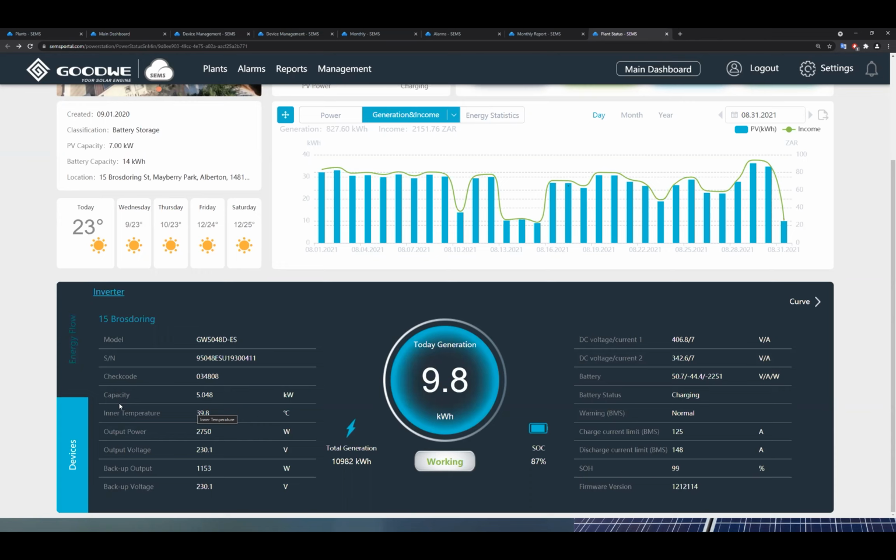Sometimes when we don't see anything here or any problems here, we do export that data, because then we can see 1 minute interval data, and that will give us a better indication of exactly what has occurred. As you'll see, this is live snapshot data. So it's the current live snapshot of what was going on in your inverter in the last 5 minutes.